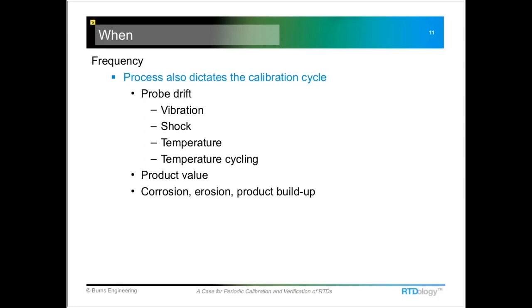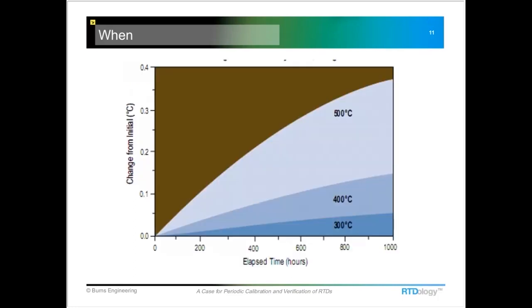Also, I've had situations where the product can build up on the temperature probe or the thermowell, and it tends to insulate it from the process fluid temperature, and you start getting more stem conduction and a bad temperature reading. So those are all guidelines to look at when you're trying to determine what frequency you need for calibration.